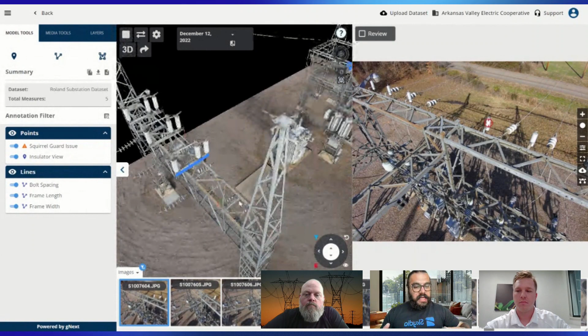Levi, we had this discussion earlier where you said most of the measurements are already pretty standard through that substation-like environment. So by measuring a known reference and finding it's pretty tight, that means the whole model is pretty tight, and you have some pretty good measurement capability through there. And the incredible part is none of this was done with an RTK system, and we're still able to find this.